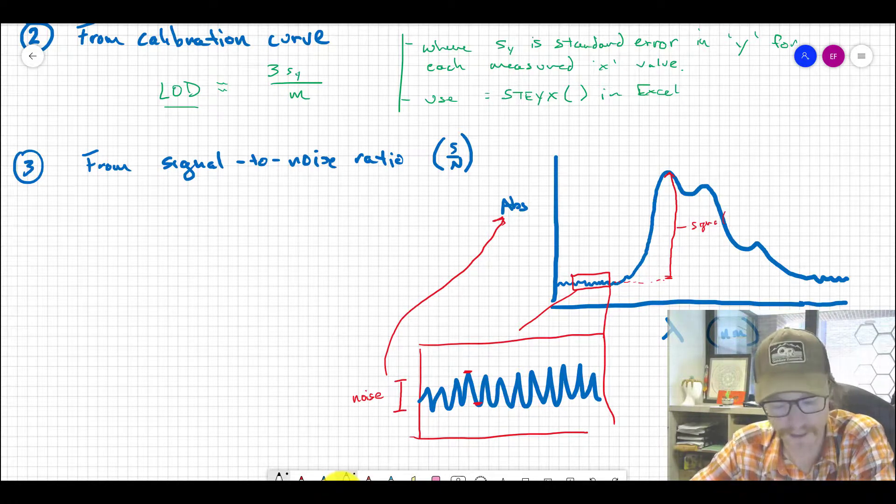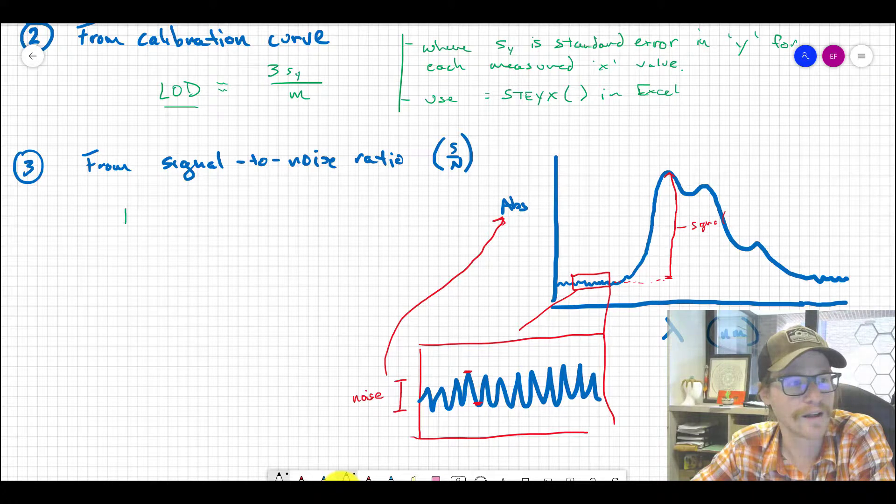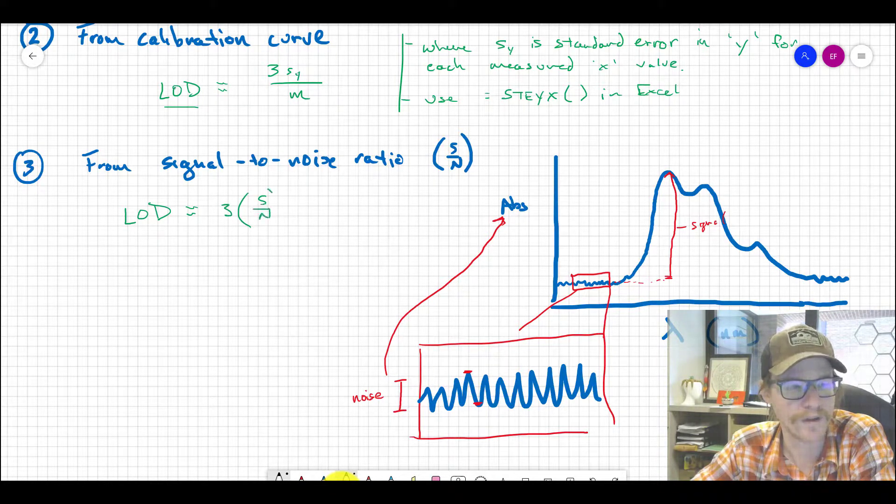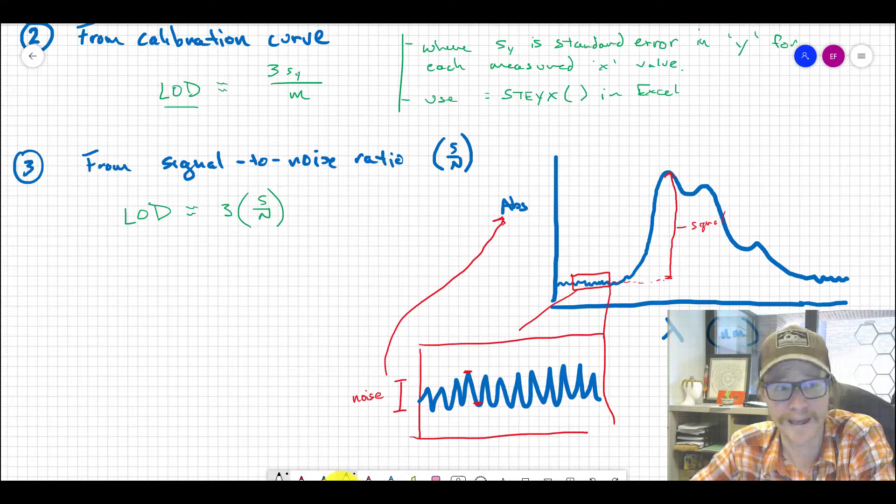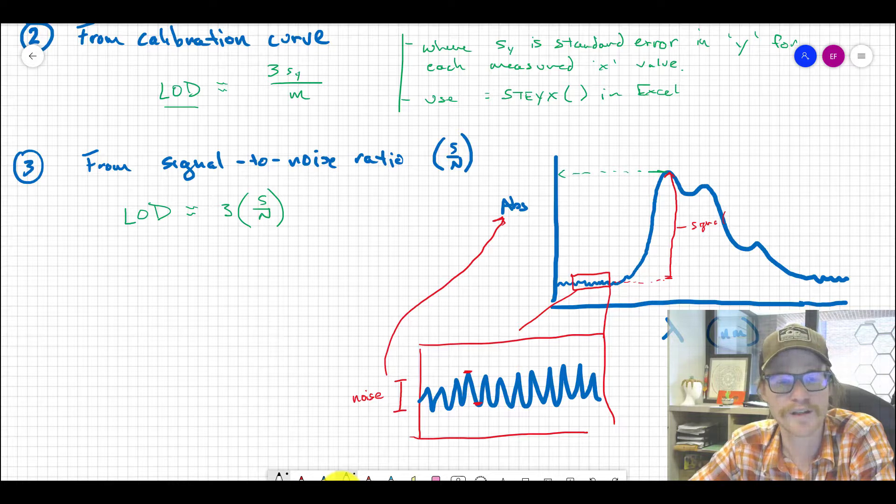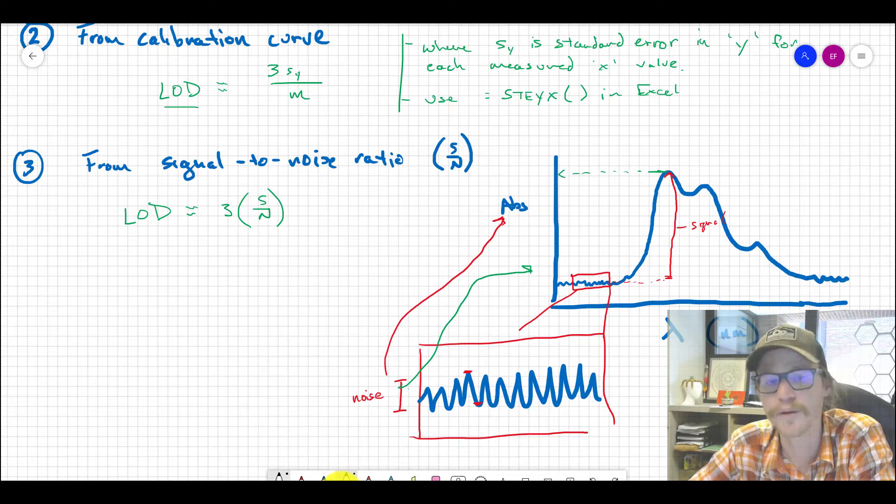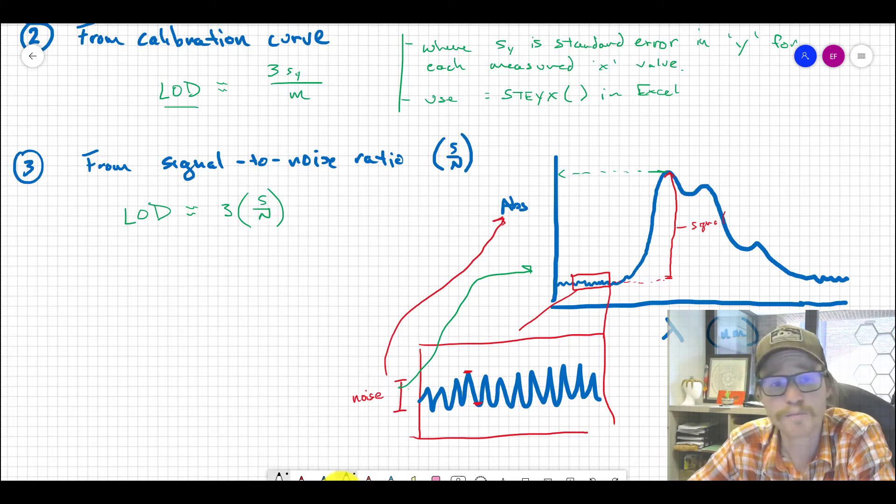For an estimate of LOD using this method, we can take three times the signal-to-noise ratio—signal being the value measured in absorbance units versus the noise value in absorbance units. This is a quick and dirty way, but it's nice because if you have a spectrum, you can quickly estimate the detection limit just by looking at it. You don't even need a calibration curve.